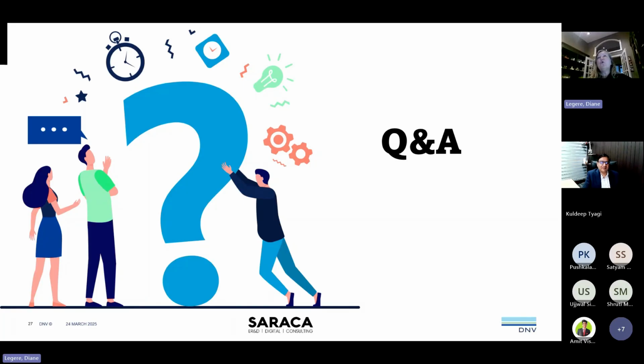The MDR as a whole, as I said, if it was up to me, I would write a separate one for class 1 devices, but the MDR is applicable from class 1 right through to class 3 implantable. All the relevant parts apply to all. So what would be a good reason to not do usability studies for your device? I think that would be the question. How could you justify not doing them? Absolutely. No, I agree.